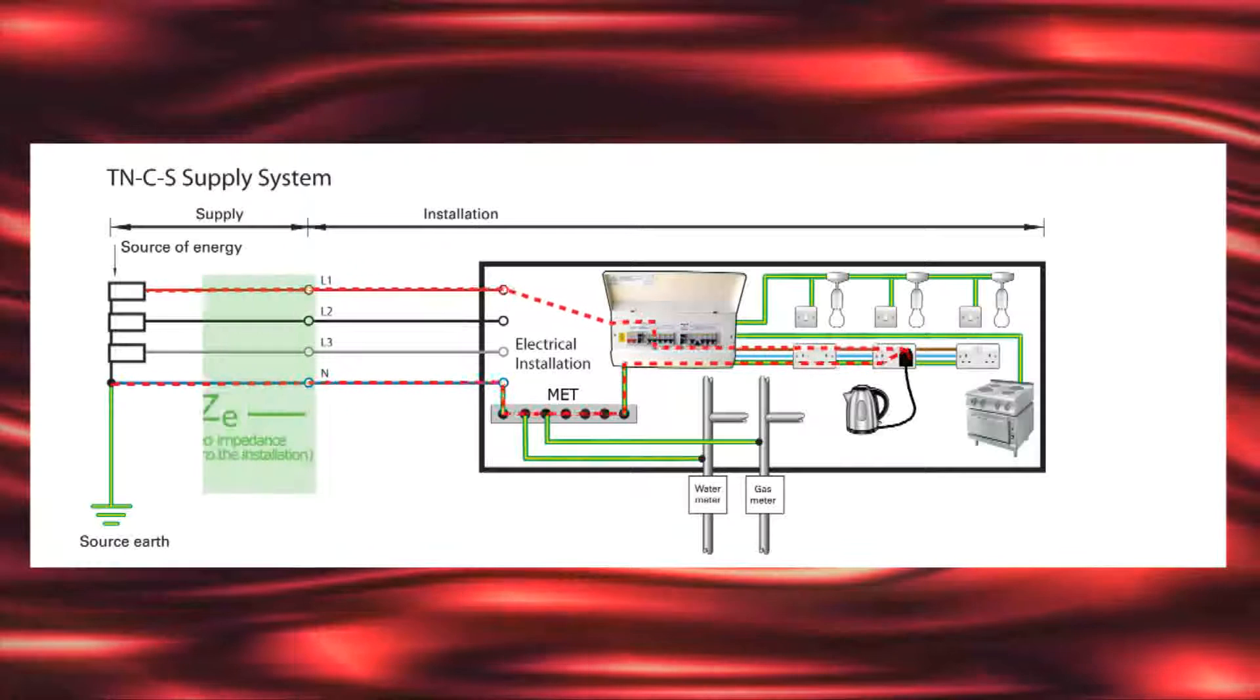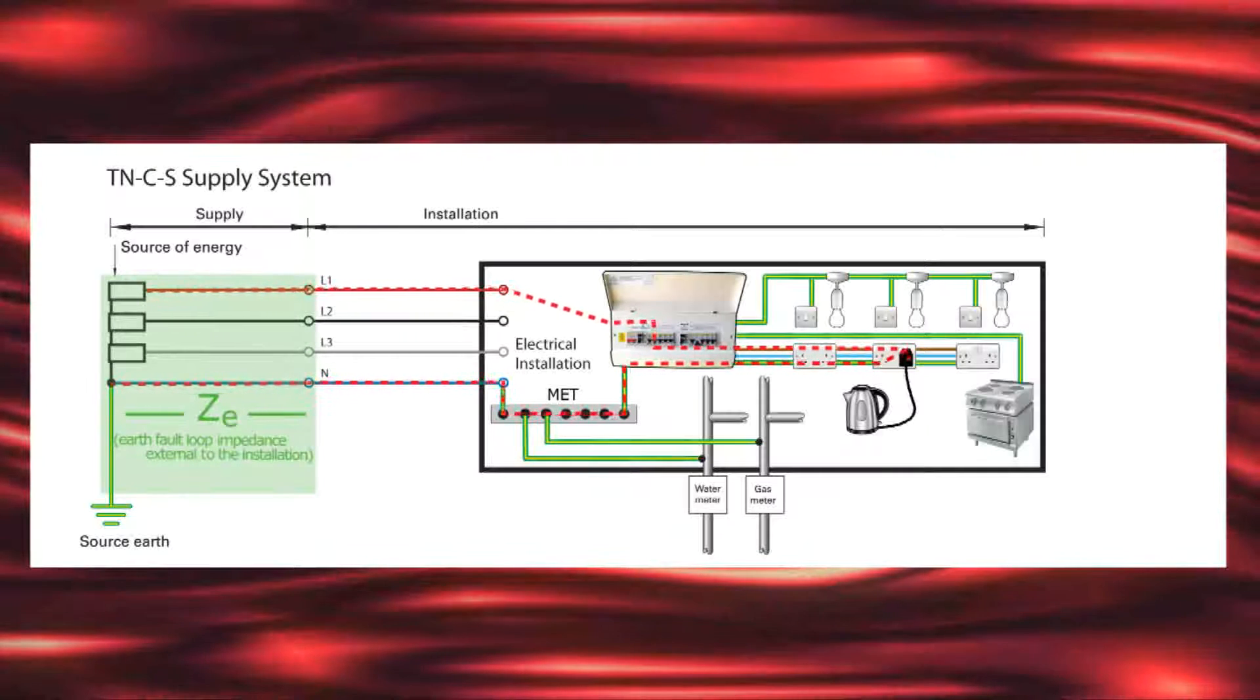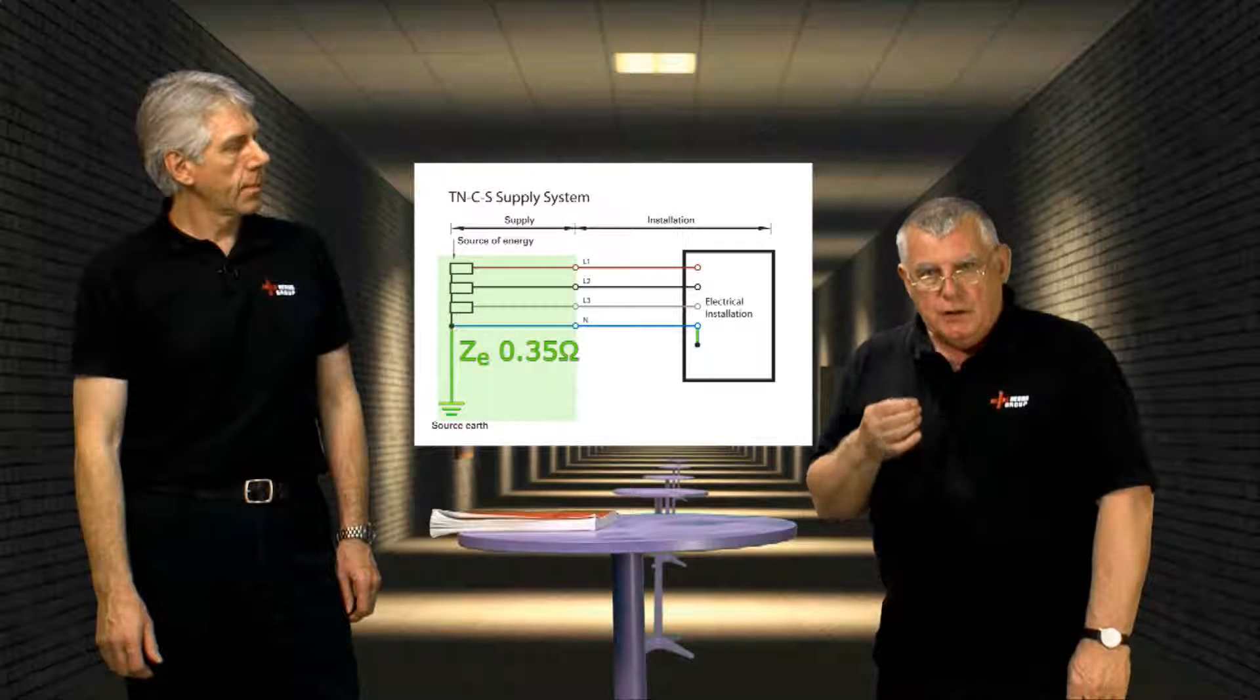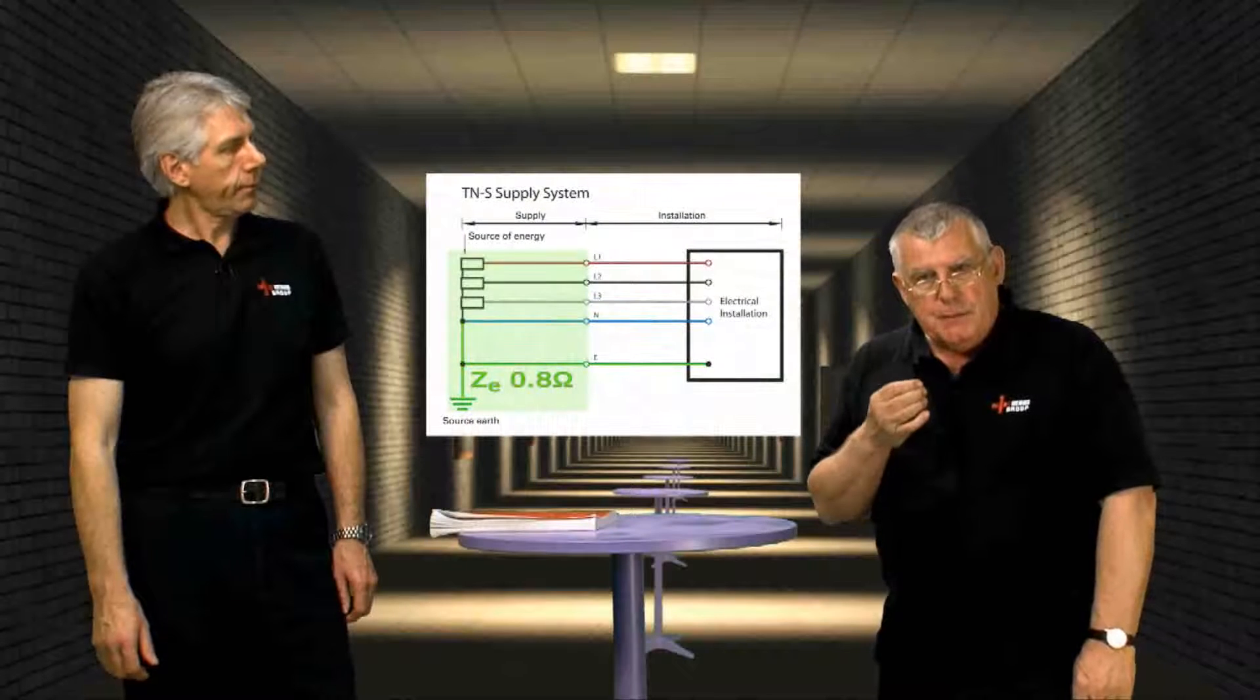It's important to point out that the portion of the earth fault loop path external to the installation is known as ZE. Electricity distributors declare values for ZE on a TN-C-S system to be 0.35 ohms and on a TN-S system to be 0.8 ohms. So the principle of automatic disconnection of supply is that, using Ohm's law, the low impedance path to earth means that earth fault currents should be of high magnitude, making them easier for the circuit protective device to distinguish against overloads and disconnect the supply quickly.